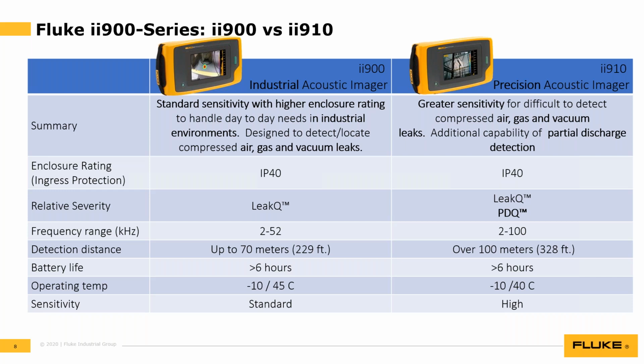This might be the best slide. The 910 is really building on the 900. So everything the 900 has, the 910 has also, but from a sensitivity or leak detection standpoint, it's better. Anything the 900 can detect, the 910 can also, but smaller leaks or leaks at a larger distance could be detected by the 910.